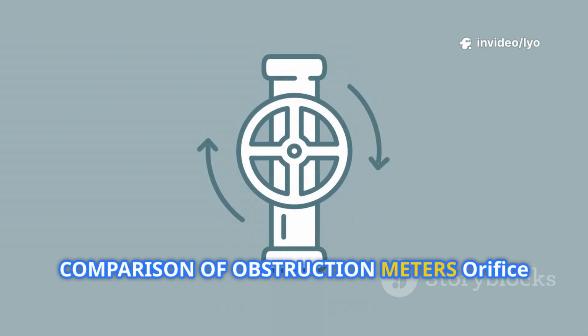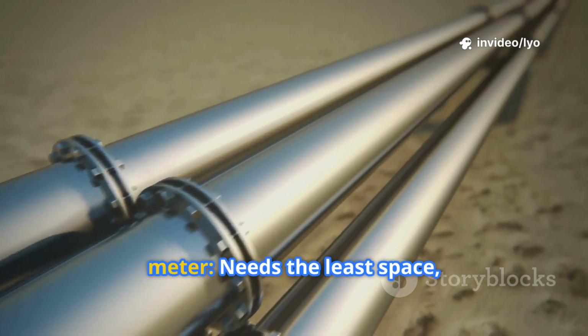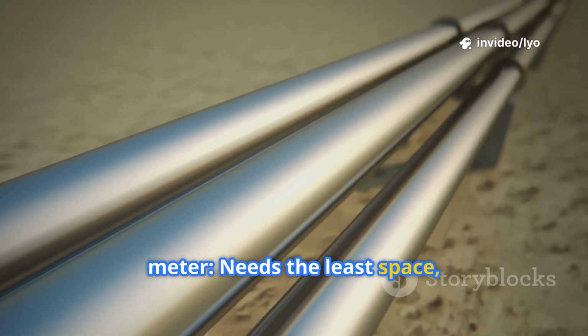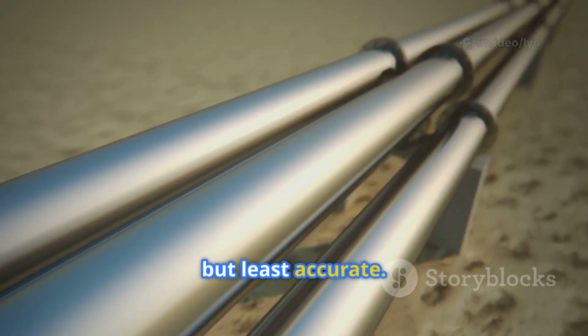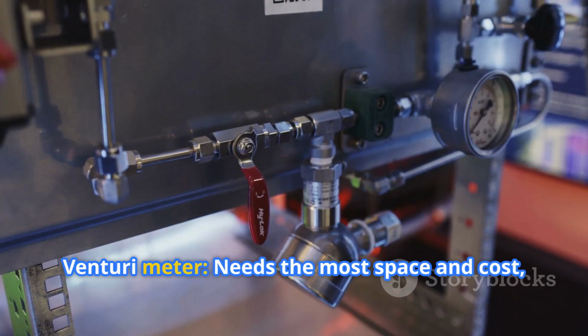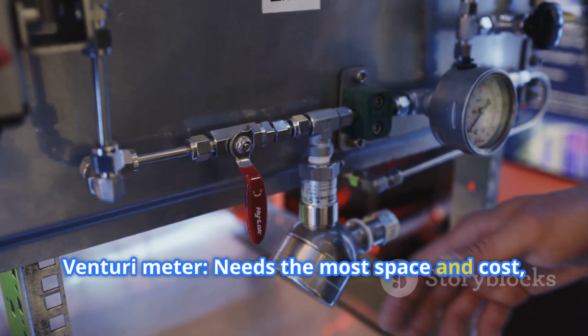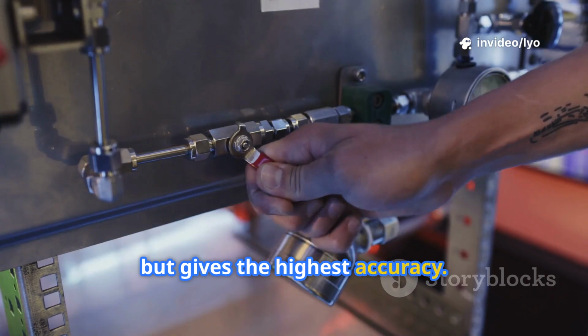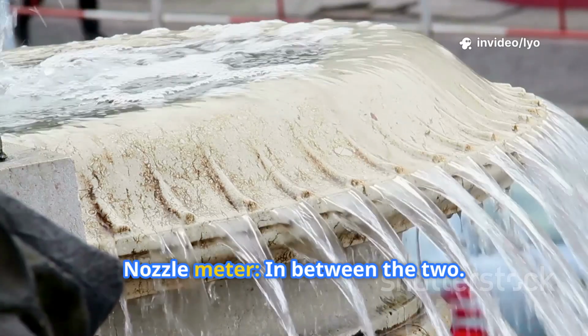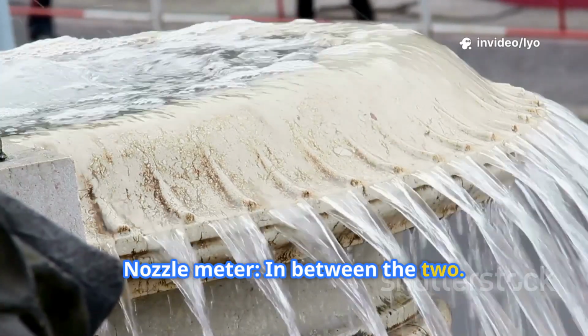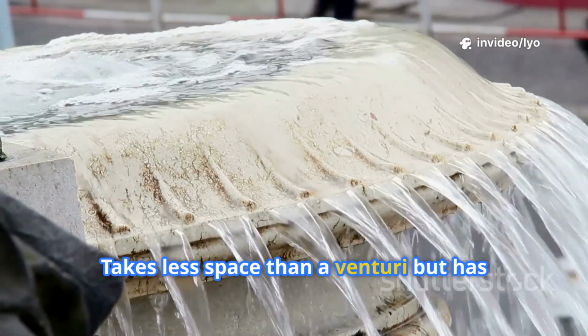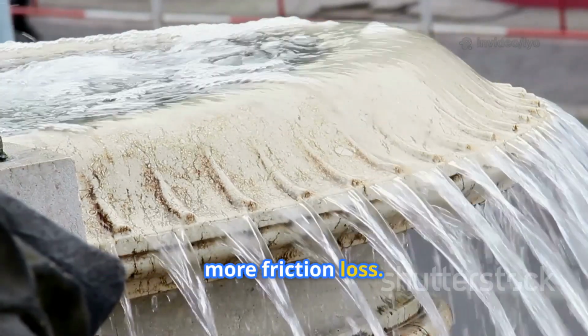Comparison of obstruction meters. The Orifice Meter needs the least space and has the lowest cost, but is the least accurate. The Venturi Meter needs the most space and cost, but gives the highest accuracy. The Nozzle meter is in between the two: it takes less space than a Venturi, but has more friction loss.